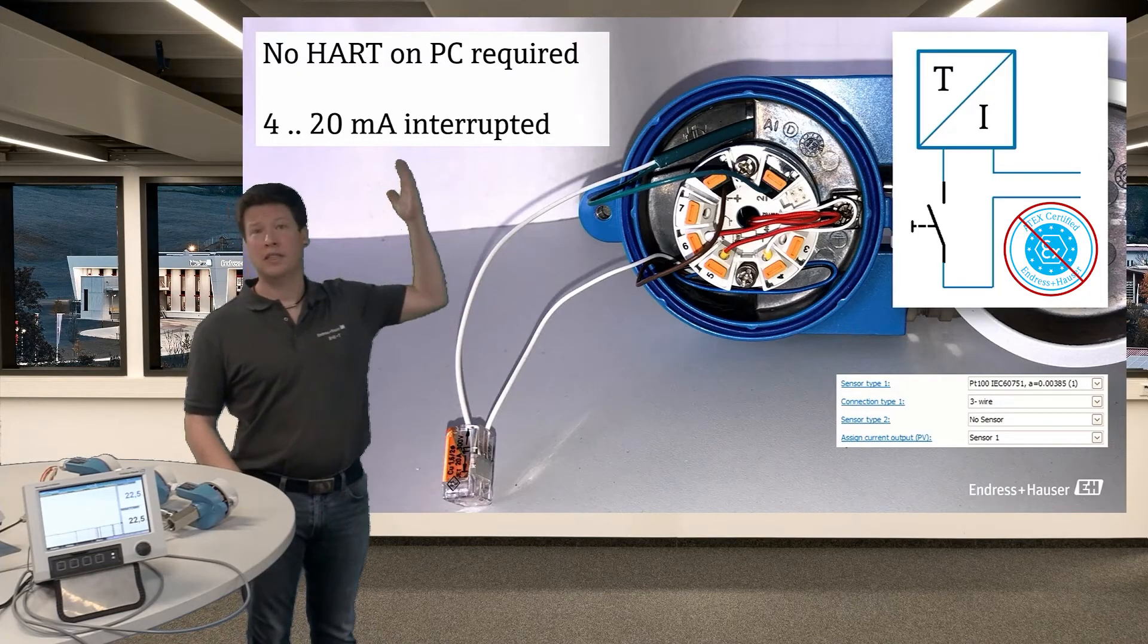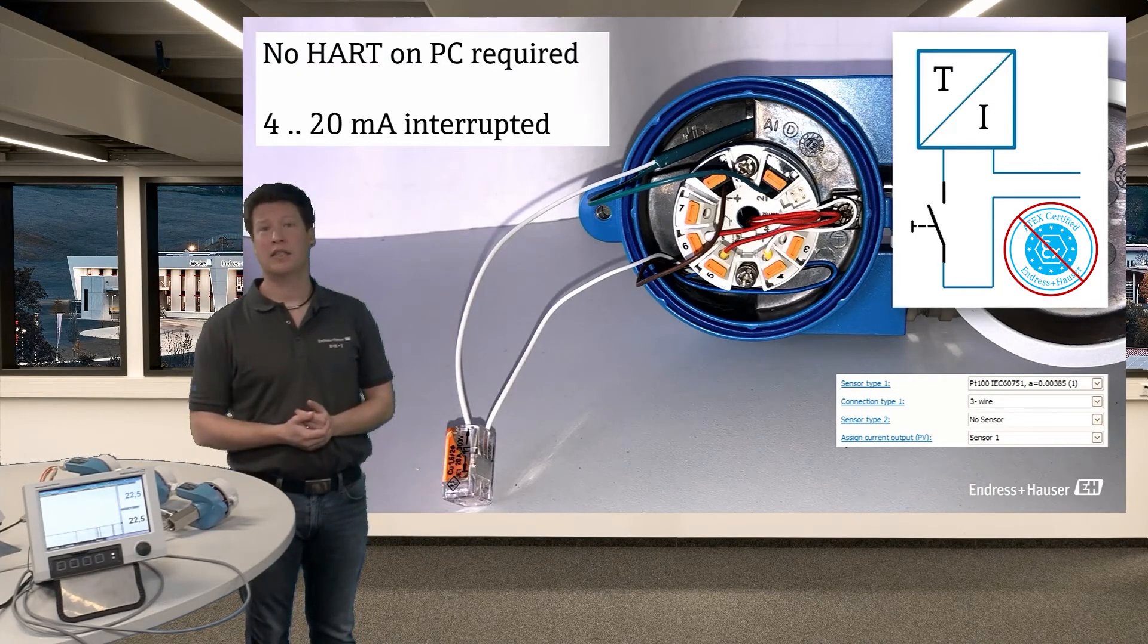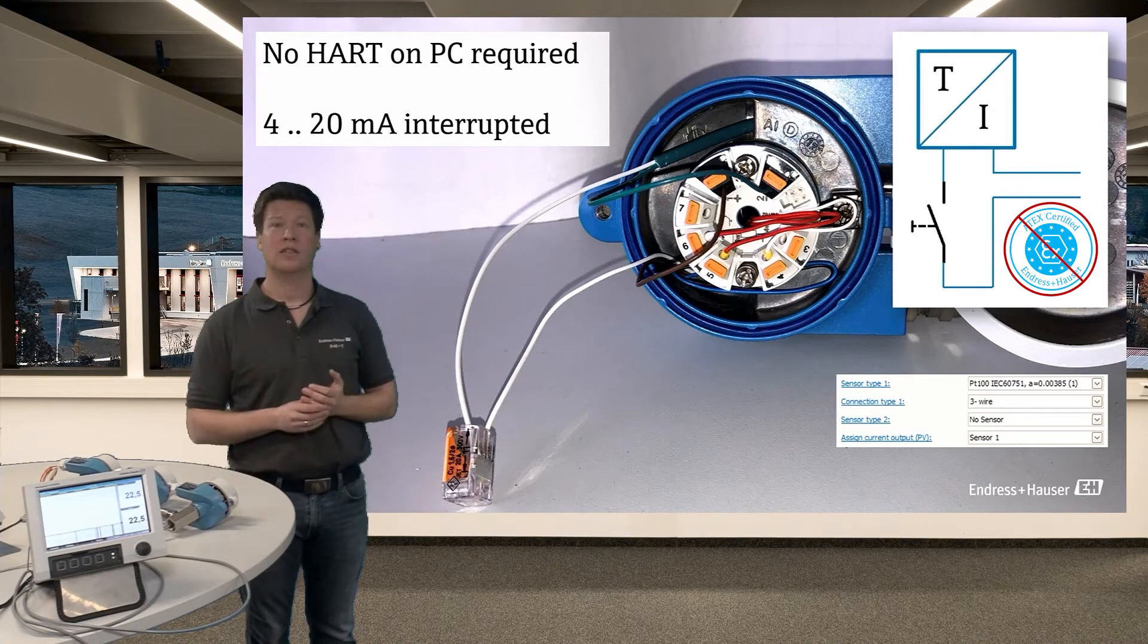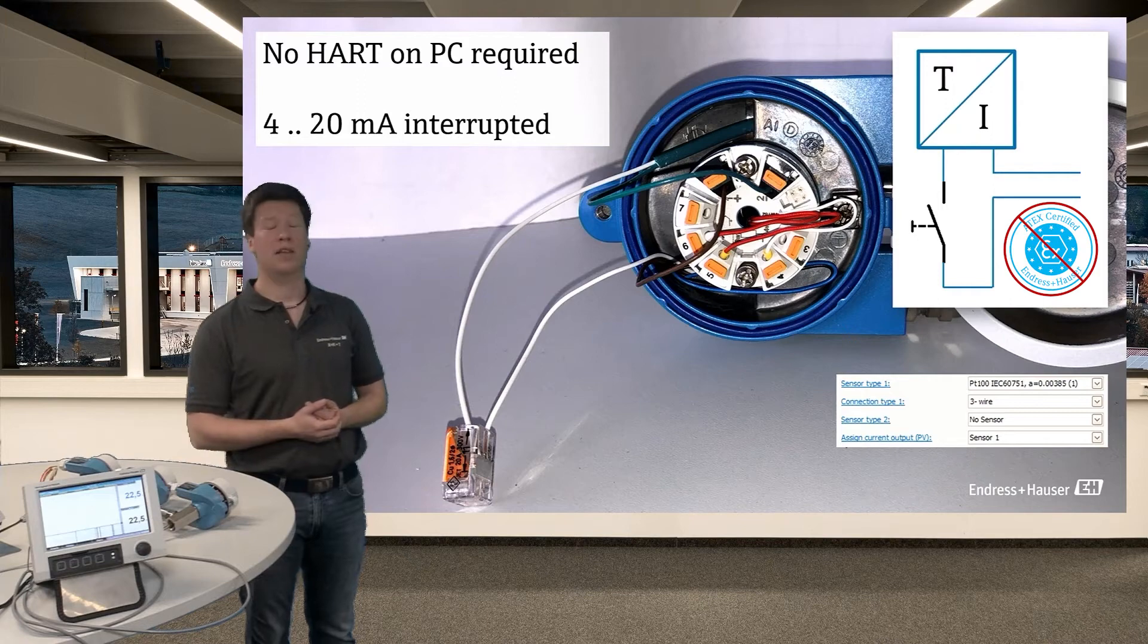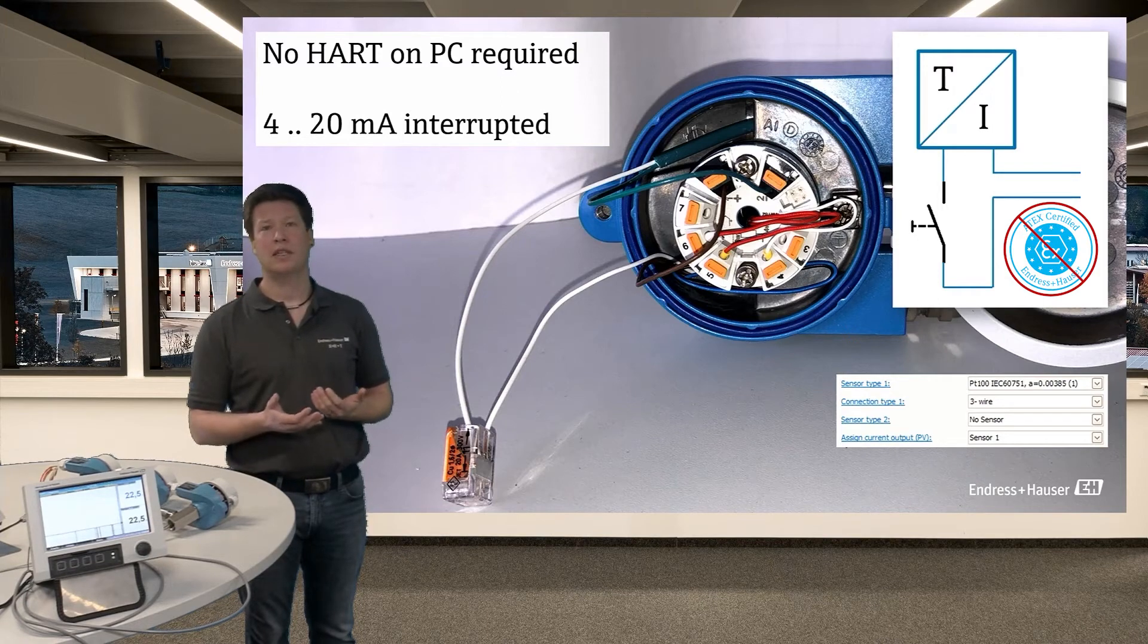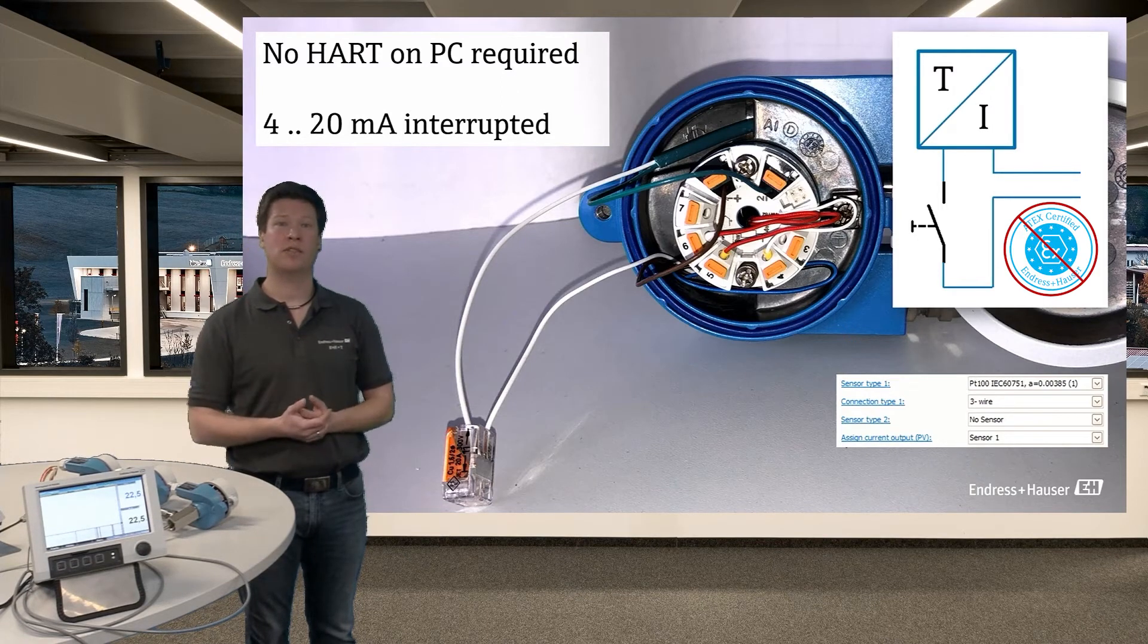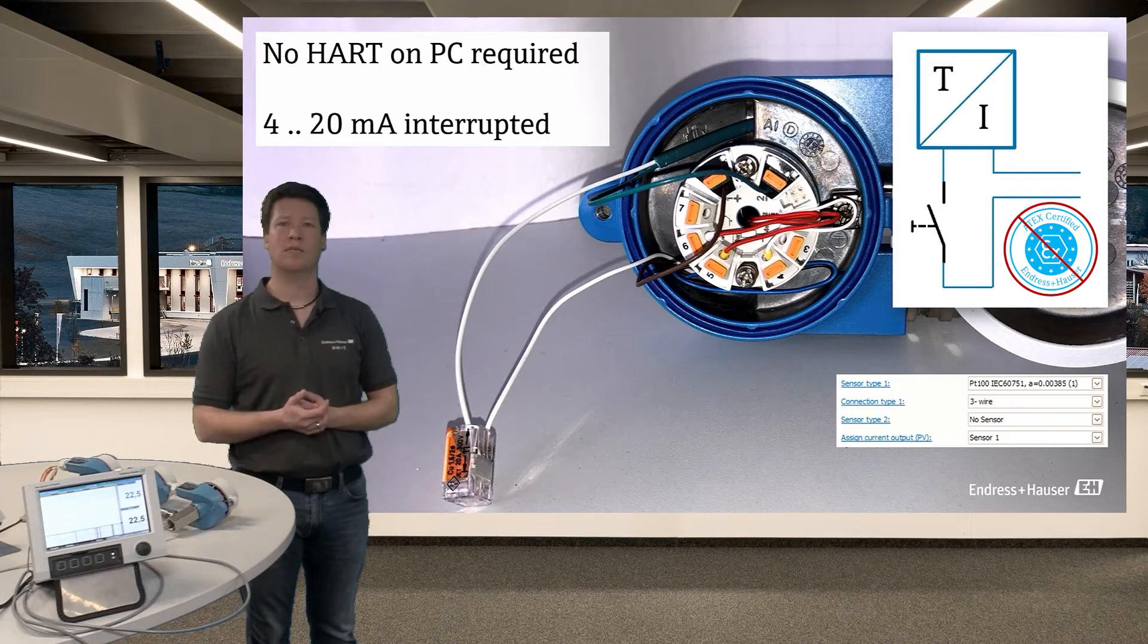Benefit is that we don't need the HART signal to be interpreted on the PLC. So no intelligent HART PLC required. The bad point about this is that we don't have a temperature signal anymore as soon as the pressure switch is activated.